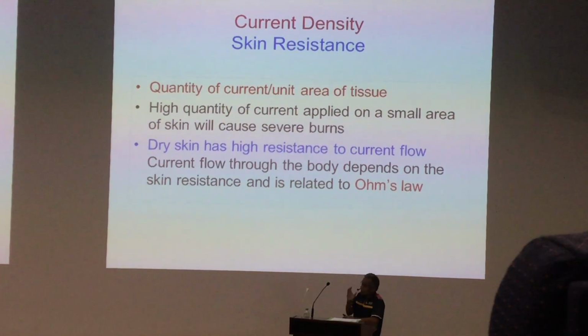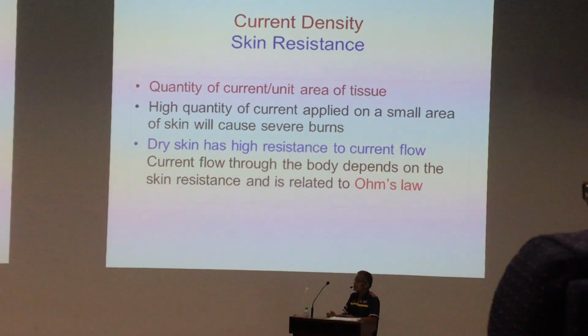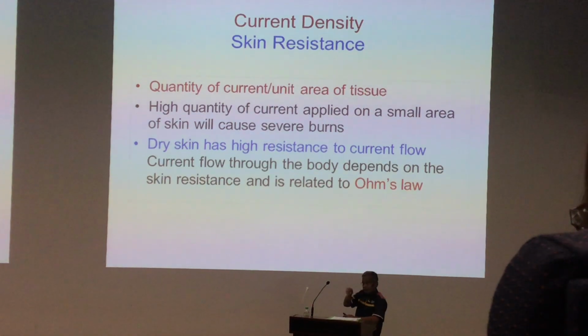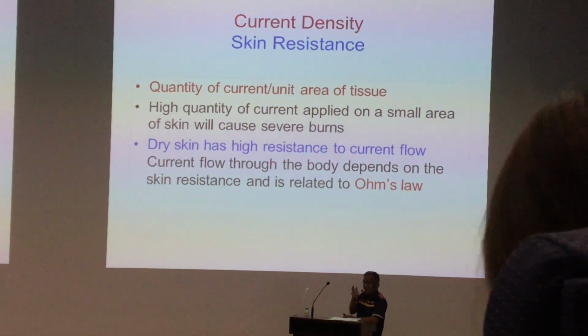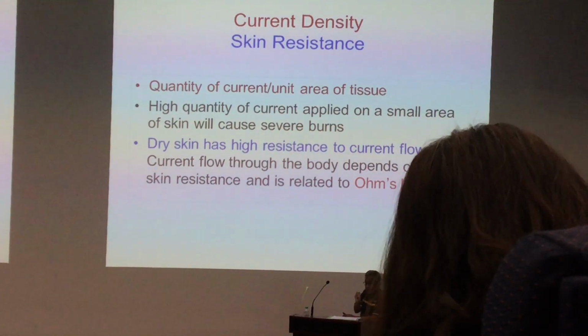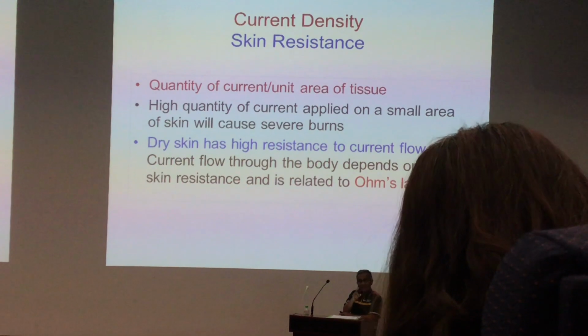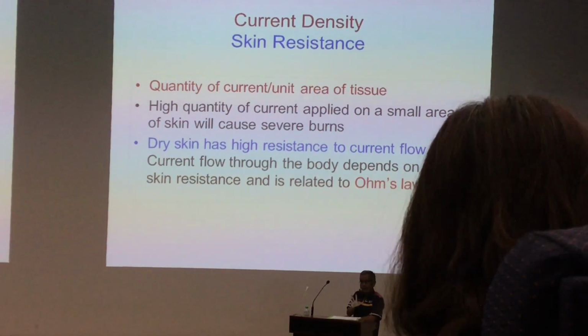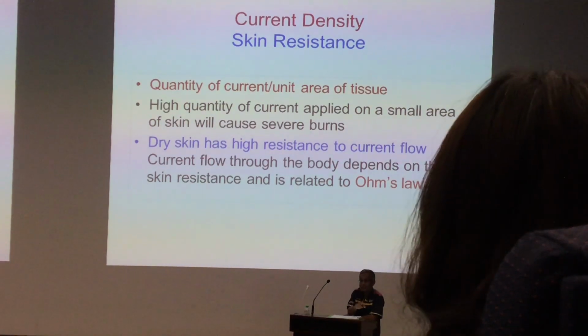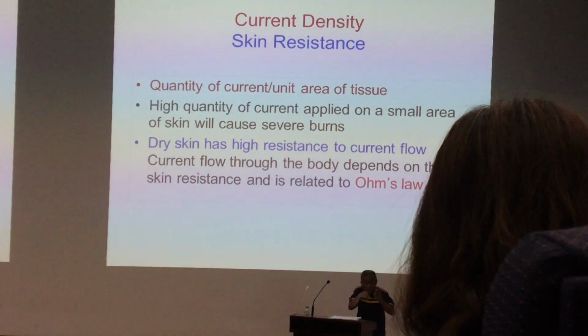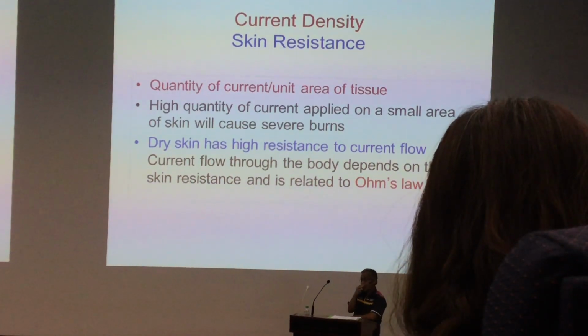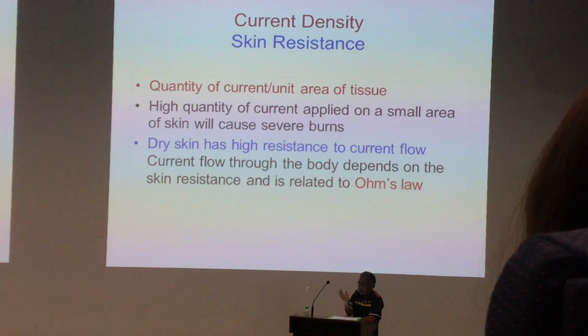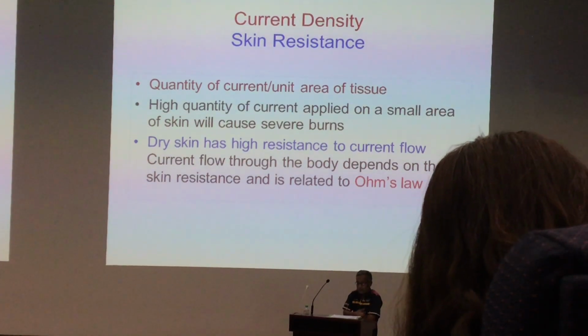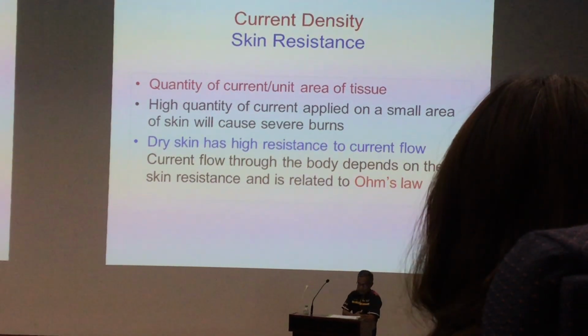What about current density? Current density is also important because it may determine whether the area is burned or not. If you pass a very high density of current through one small area, it can focus there and cause a burn. For example, with a surgical diathermy plate, if you don't put it in contact properly with the skin, it can cause burn because the current density will be focused in one small area. That's why when you put the diathermy plate, the whole plate should be placed onto the skin nicely, without any area not in contact with the skin.